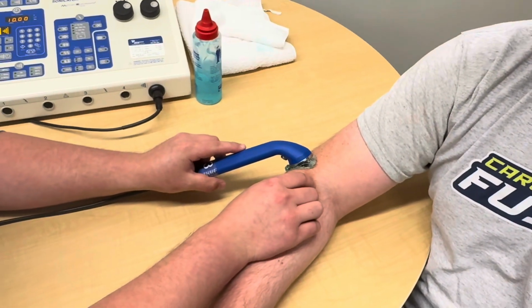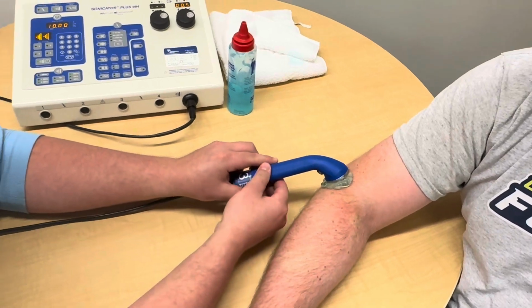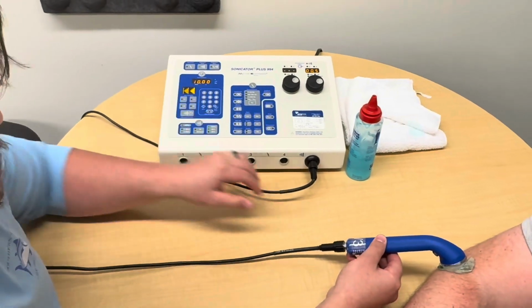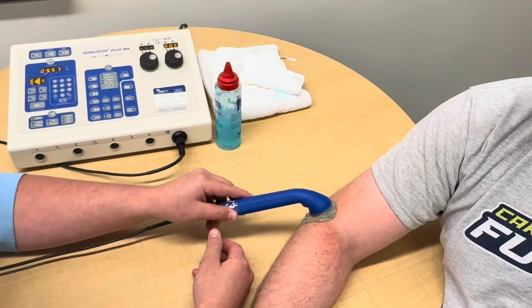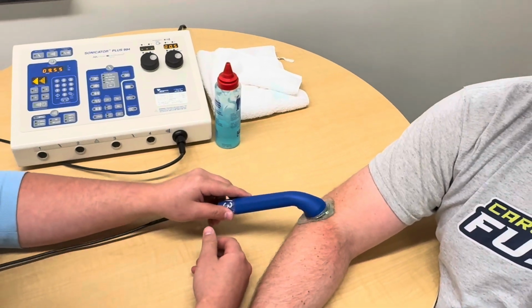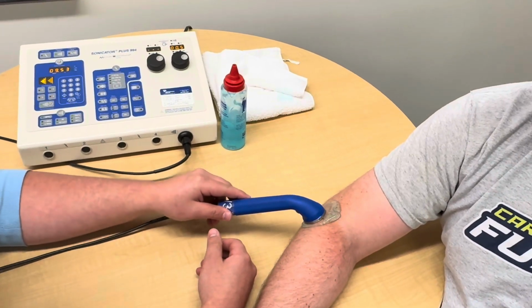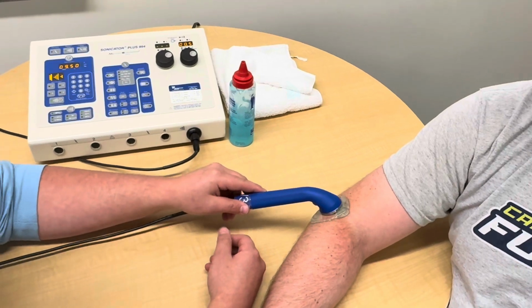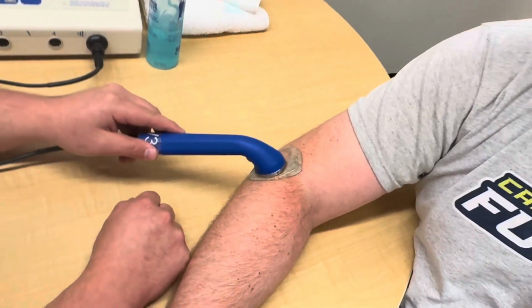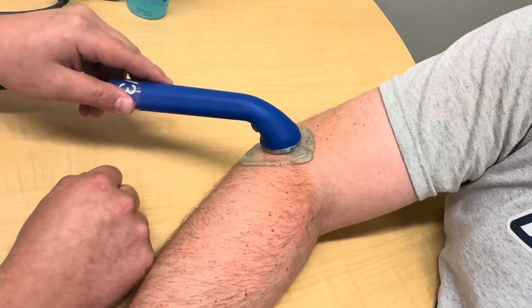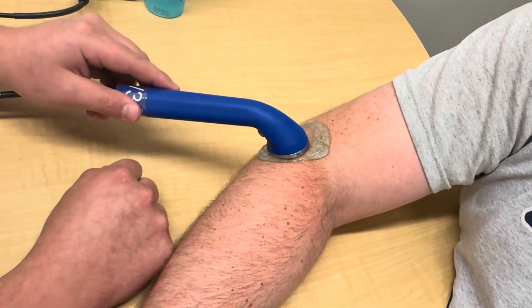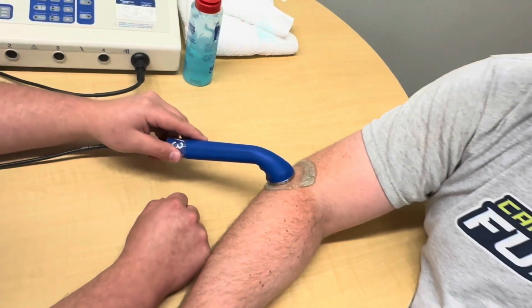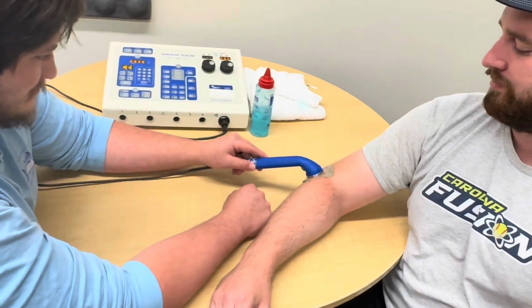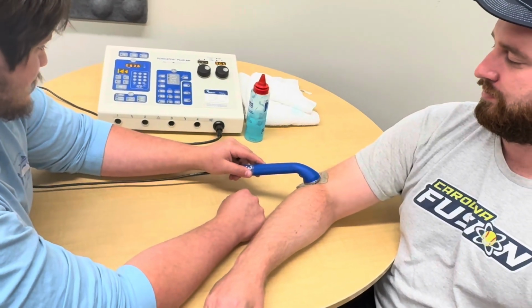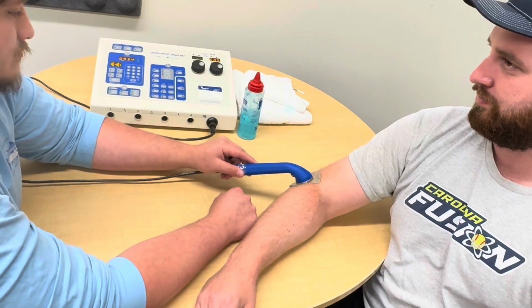Next, turn the machine on and begin treatment. The PT will move the probe in a figure 8 or wave pattern. It is important that the physical therapist keeps the probe moving to prevent hotspot formation within the tissue. Additionally, it is important to avoid bony prominences because it can result in periosteal burns. In this case, it is important to avoid the olecranon, lateral epicondyle of the humerus, and the head of the radius. How's this feel, Nick?